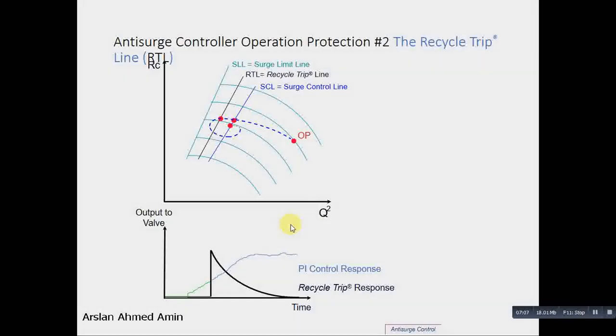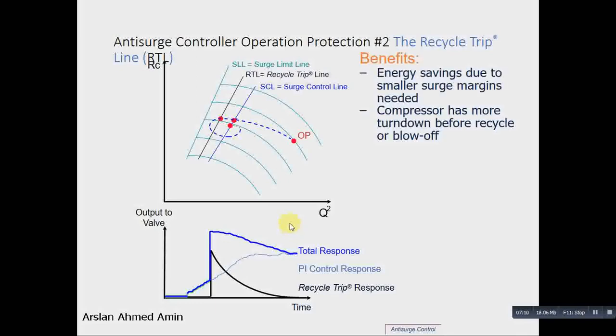Benefits: energy savings due to the smaller surge margin needed. Compressor has more turndown before recycle or blow-off. Surge can be prevented for virtually any disturbance. We can reduce this margin because we know that there is another margin line we have defined in-between. When the operating point will touch this line, suddenly the recycle will open, which will protect the compressor. In this way, this margin can be reduced. But normally, it is kept at 10%, and the recycle trip line is kept at 5% with respect to the surge limit line.